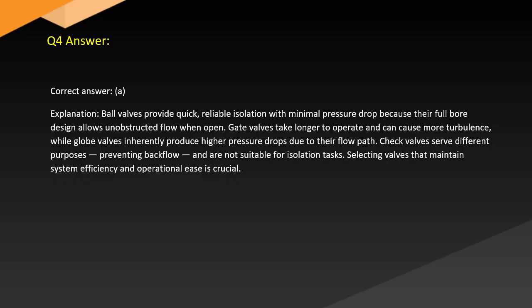Ball valves provide quick, reliable isolation with minimal pressure drop because their full-bore design allows unobstructed flow when open. Gate valves take longer to operate and can cause more turbulence, while globe valves inherently produce higher pressure drops due to their flow path. Check valves serve different purposes, preventing backflow, and are not suitable for isolation tasks. Selecting valves that maintain efficiency and operational ease is crucial.